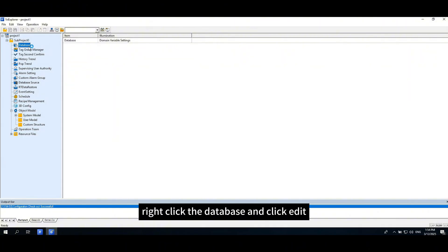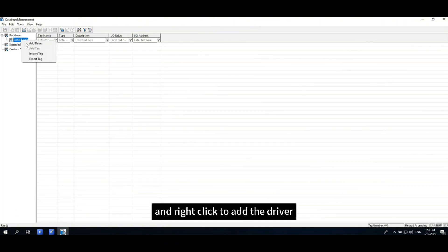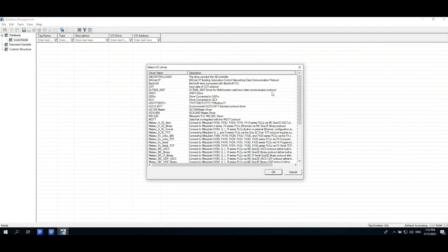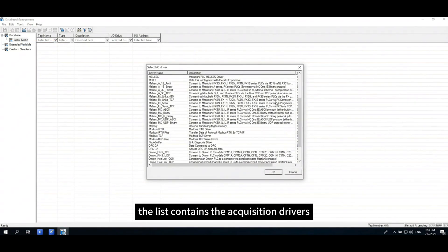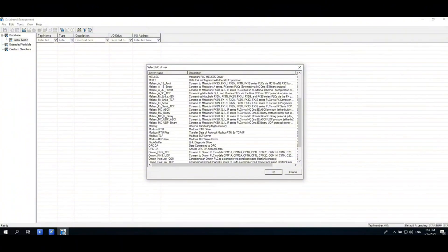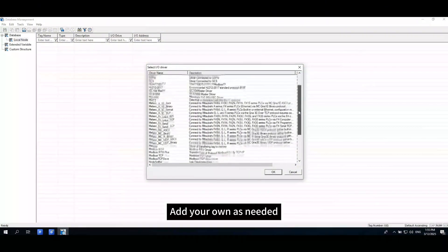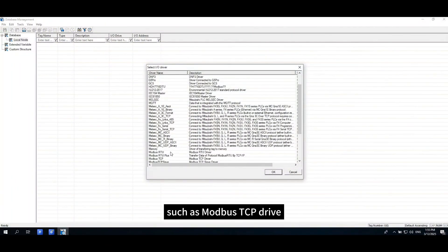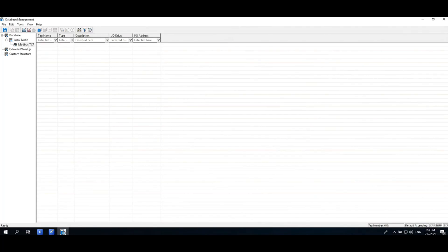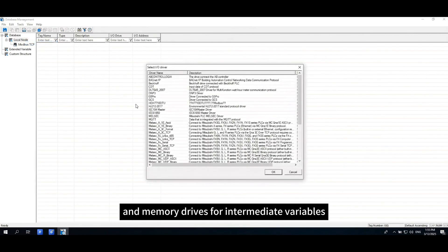Right-click the database and click edit. Click the local node and right-click to add the driver. The list contains the acquisition drivers. Add your own as needed, such as Modbus TCP drive and memory drives for intermediate variables.